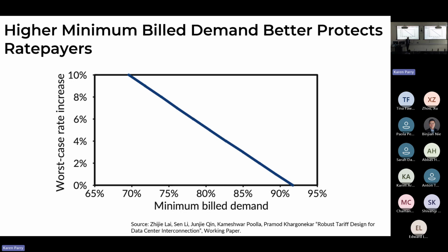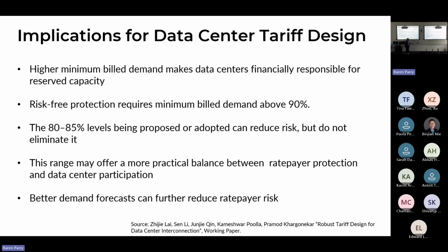This is an example result we have. On the x-axis is the minimum billed demand as a percentage of nameplate demand, and on the y-axis is the worst case rate increase on the rest of the consumers. As your minimum billed demand goes up, the exposure of residential consumers goes down, as you'd expect. We have models to create these curves, and our general conclusion is that it takes about 90% to ensure consumers aren't impacted.